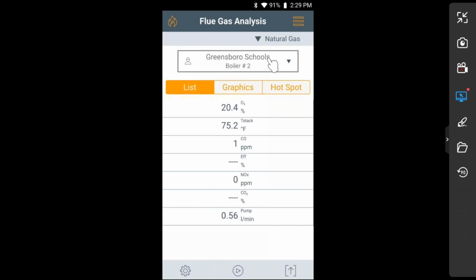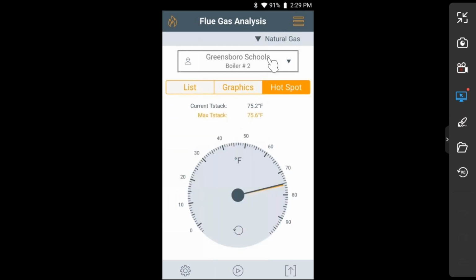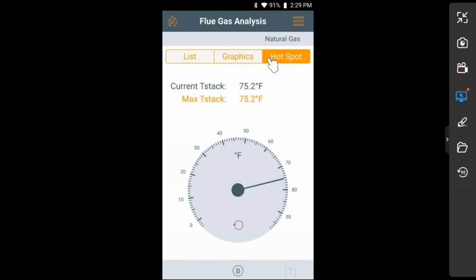You'll also see what we have up here is called hotspot. And what the hotspot is, and they use this a lot in Europe, they take a combustion efficiency test at the highest stack temperature in the stack where they're sampling. So what they do is they turn the instrument on and they put the probe in the stack, and it's going to show them where the hottest stack temperature is. And wherever the hottest stack temperature is in the stack, that's where they're going to take their reading.